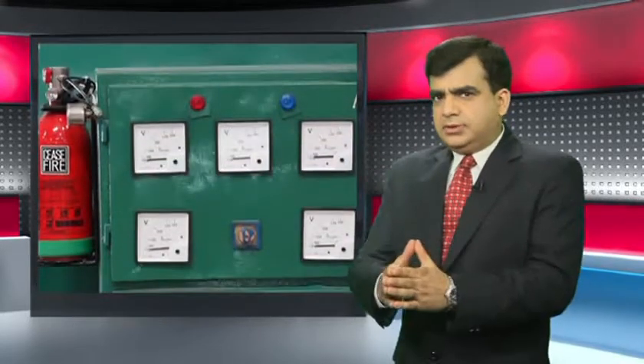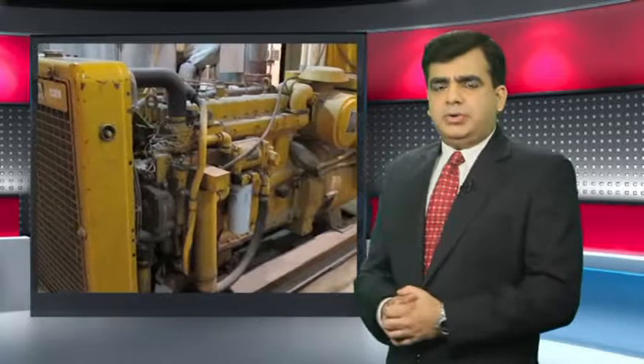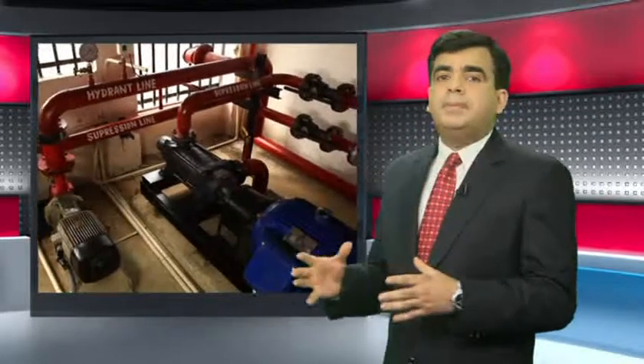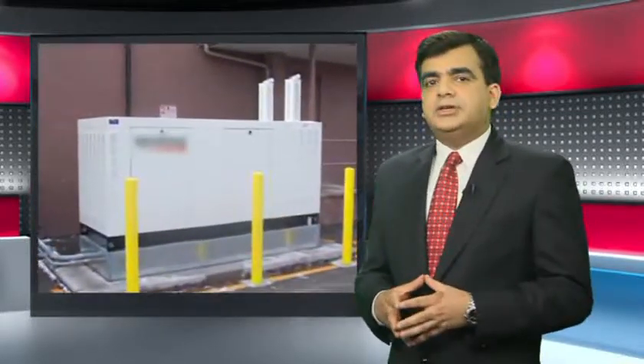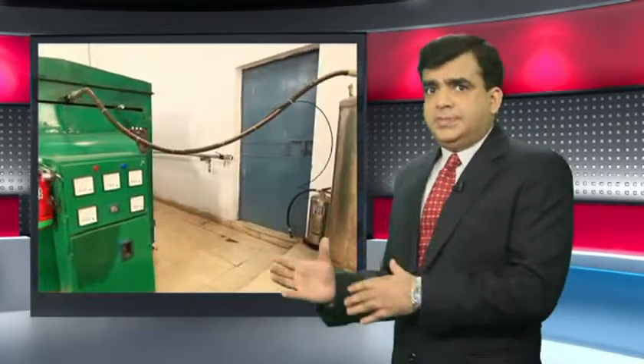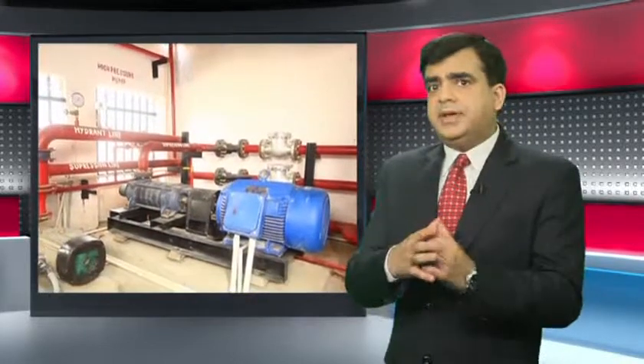On receiving the alert signal from detectors, the control panel sends a signal to activate the system and release the extinguishing agents. In case it's a large-scale generator, water, the extinguishing agent, is stored in a reservoir or tank that is connected to a pump. For smaller and medium generators, the extinguishing agent is delivered through a self-contained pulse mist-based system. The water, either from the cylinder in case of a pulse-based system or in the tank in case of the pump-based system, makes its way to the nozzle head and is converted into water mist at the nozzle point. These droplets, which are between 70 and 100 microns in size, are thrown very far by the kinetic energy generated by the compressed air.